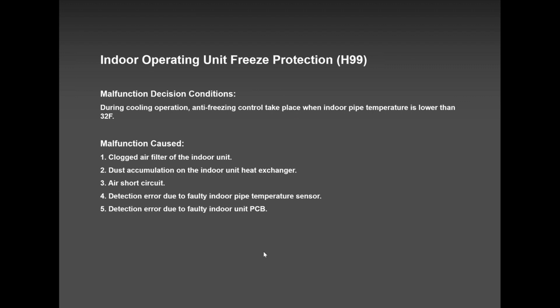H99, it will never happen in heat mode. It's an error code in cool mode or dry mode. And what that means? That means you are low on refrigerant. In all my experience with H99, in my 6.5 years with Panasonic, it's low on refrigerant.